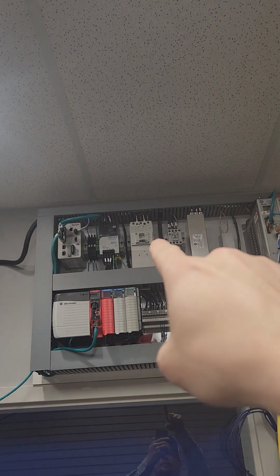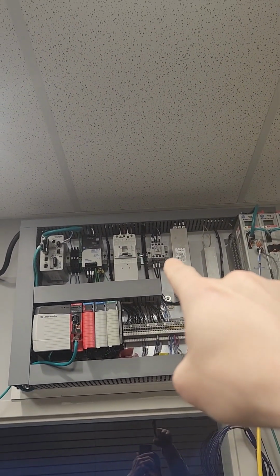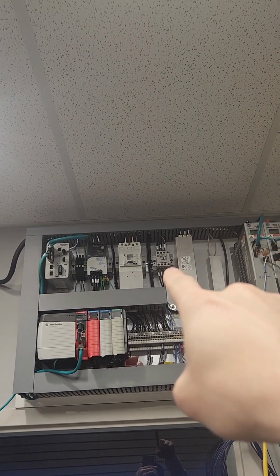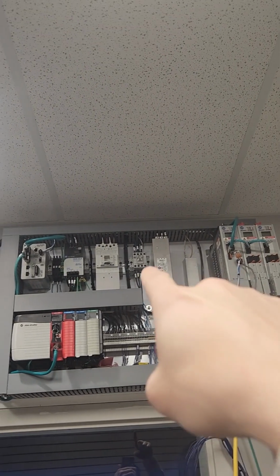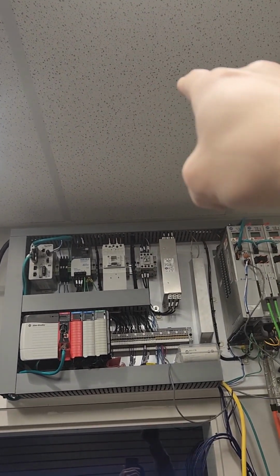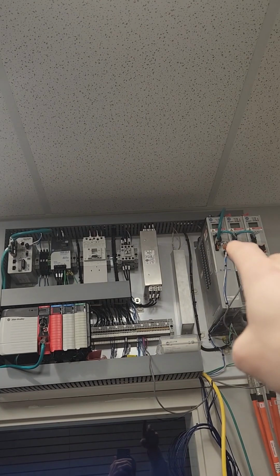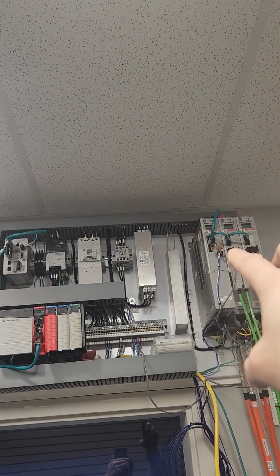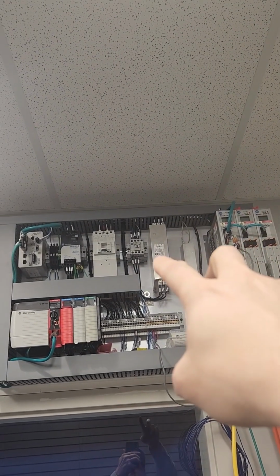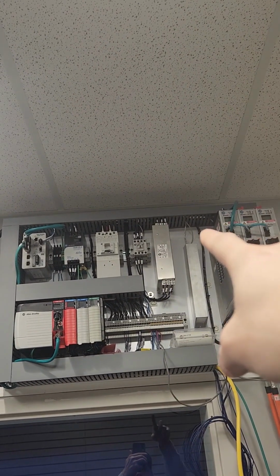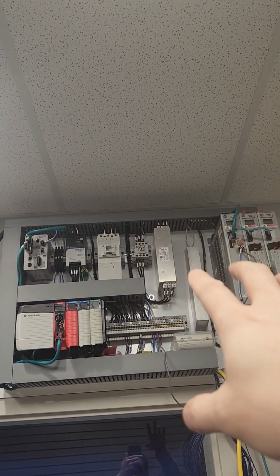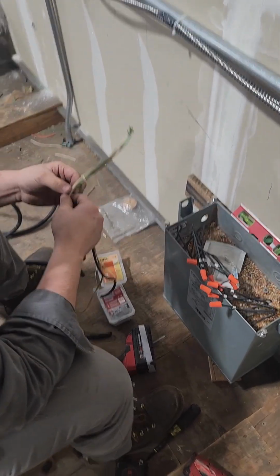So right now that's my 480 coming into my circuit breaker, goes down and up into that contactor. What we're going to do is go from the contactor enable for my servo drives up to that transformer in the roof, back down to my line filter, and then when the servo drive bus supply enables, it'll just be controlled by the contactor. It'll go through the transformer, so the transformer is not always hot. Go through the filter and we'll be able to control the robot. It's gonna work just great.